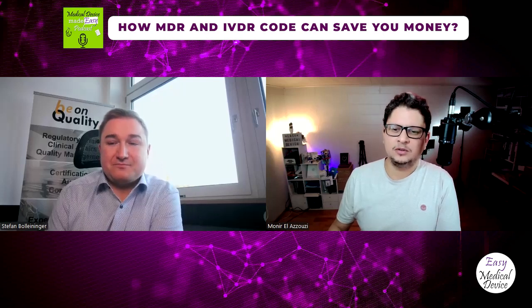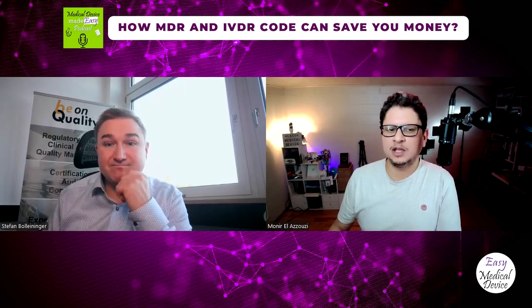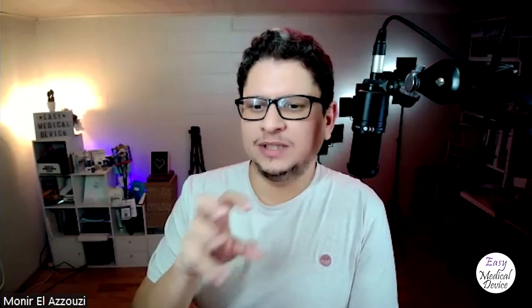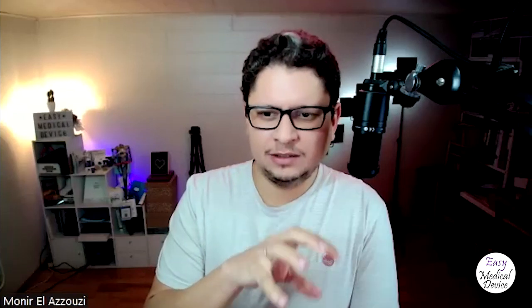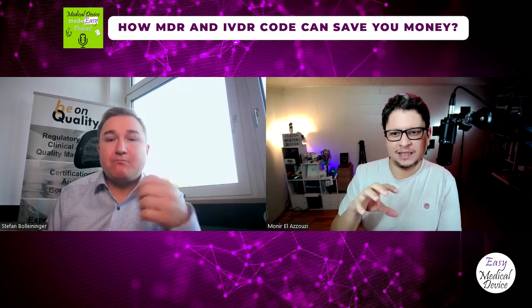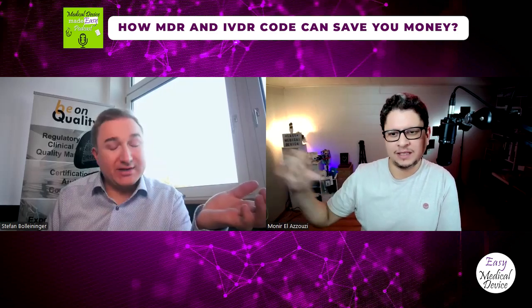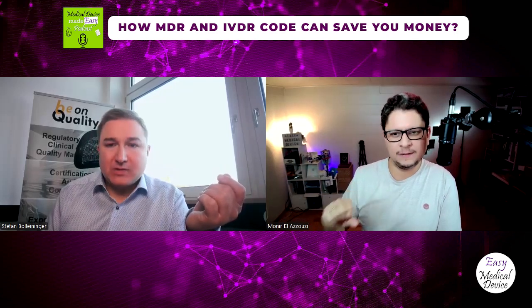Exactly. And you said something important here, because we talked mainly about choosing an MDR code or IVDR code for the selection of the auditor that will be doing the assessment. In case, for example, this is a rare code, something that is really seldom, it means that there are fewer resources maybe to do that, and maybe it can also take more time for making the assessment, I suppose.